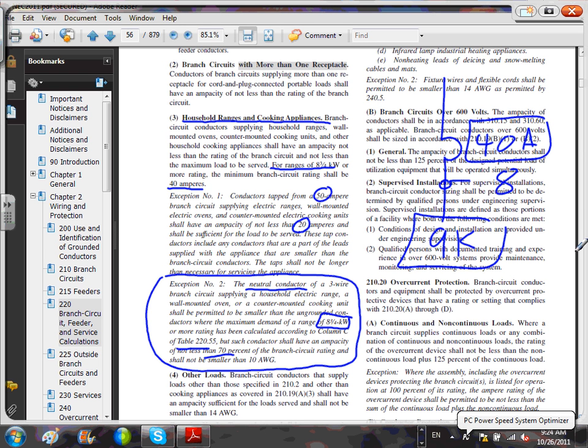What would be the circumstance where you have that? This is related to the section 1. Take this: 2 ovens and a countertop. That's a tap. Right? You take a branch circuit in a J box, you tap a bigger conductor to a smaller one to feed the smaller ones.